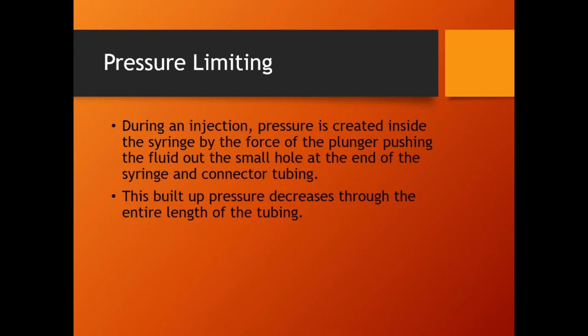One thing they don't want to happen is they don't want to stop the injection, if at all possible, right? Now, pressure limit is not an occlusion. If there's an occlusion, a tube is pinched closed, an IV needle, some kind of clog or something like that, a catheter, an occlusion is treated differently. If there's an occlusion, the injector stops, all right? You can tell the difference between an occlusion and a pressure limit, all right?